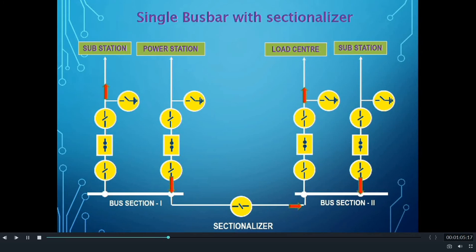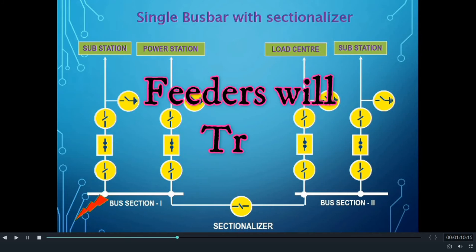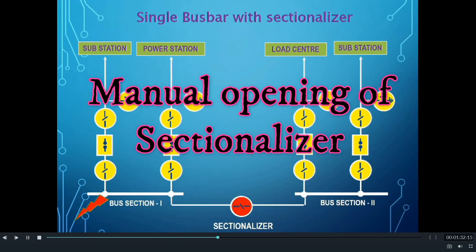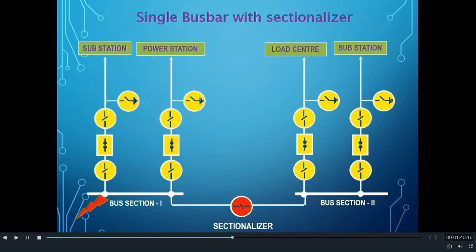For a fault in Bus Section 1, there will be fault currents flowing through all the feeders, and as a result, the relays of all the feeders will actuate and give an opening command to the Circuit Breakers. Because of the opening of the Circuit Breakers, all the feeders will get interrupted. But in a Single Busbar Scheme with Sectionalizer, we have the facility to segregate the faulty section of the bus from the healthy section. We can open the Sectionalizer Isolator and separate the faulty Bus Section 1 from Bus Section 2.